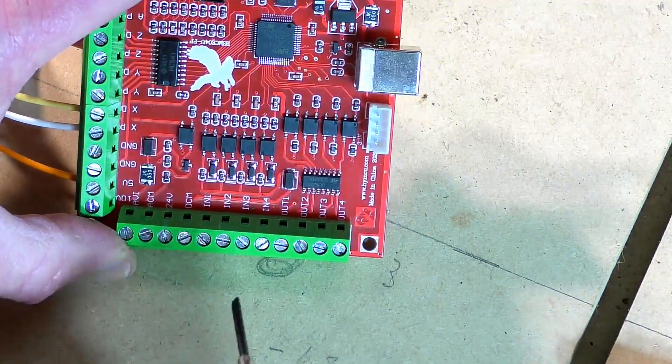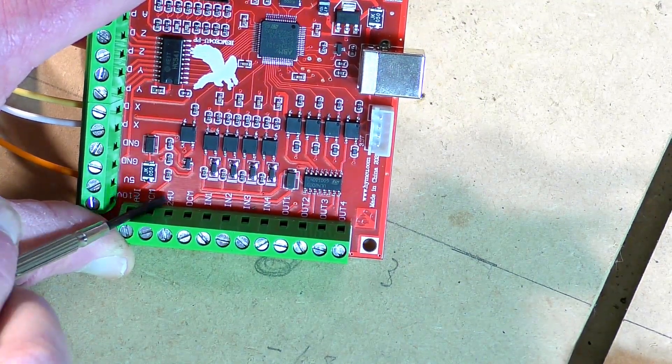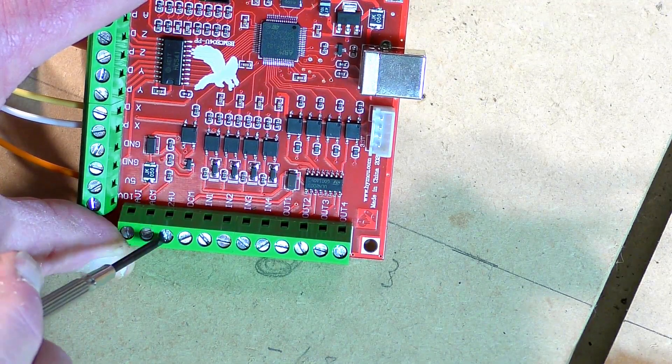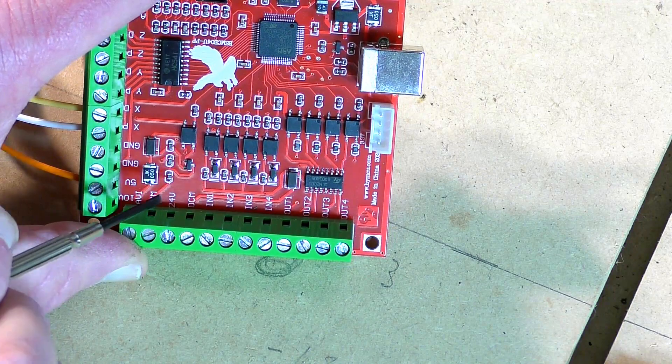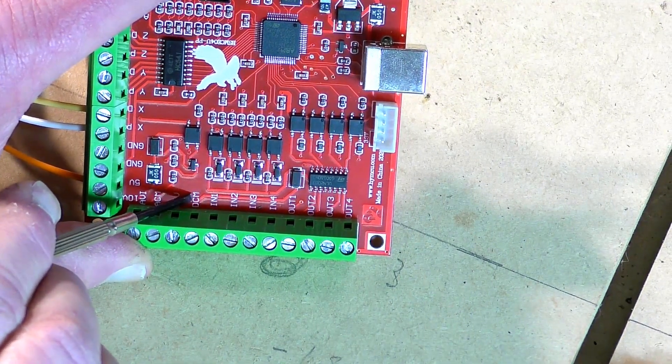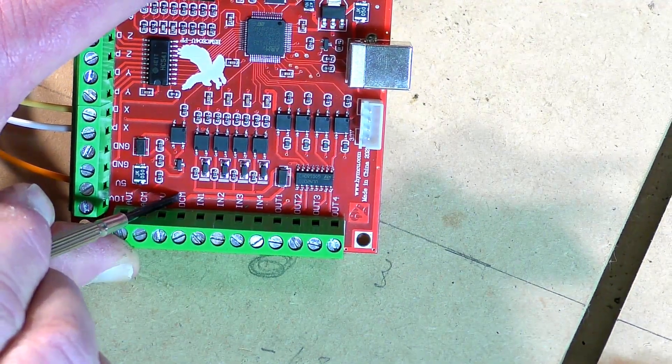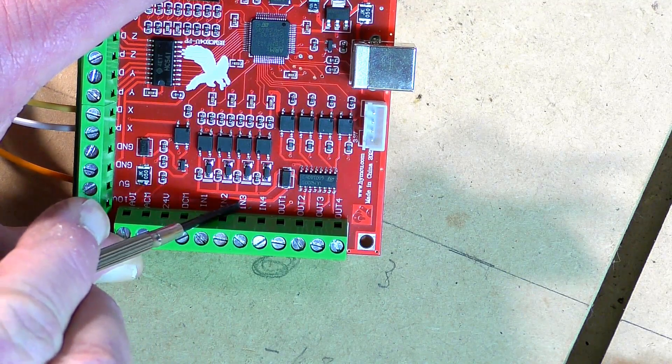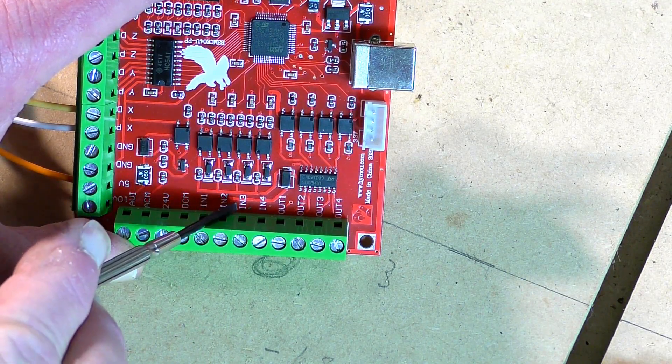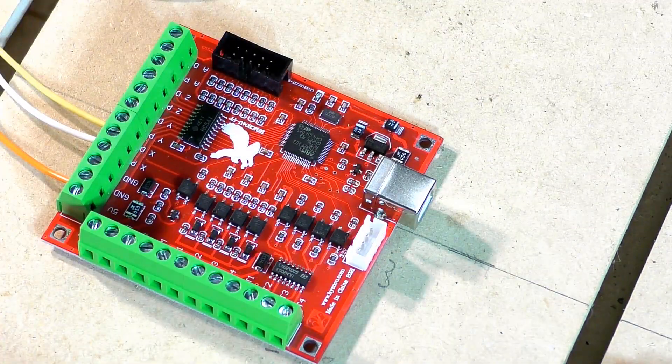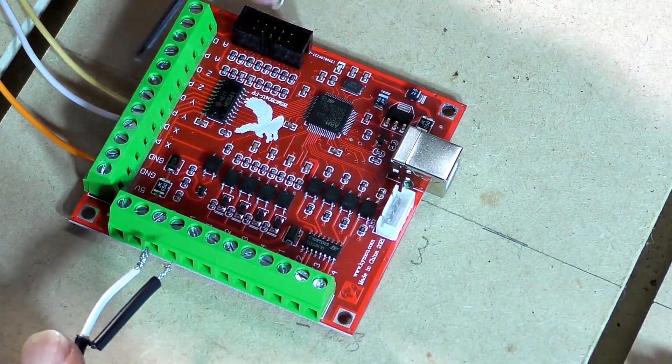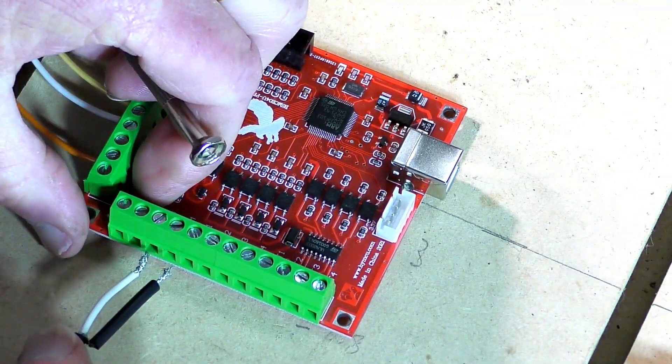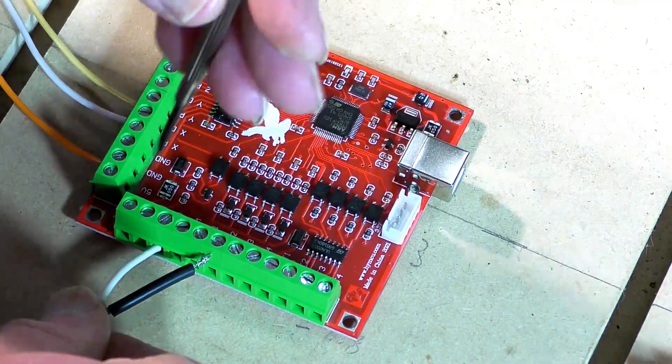This is the 24 volt side. If you notice here, this is 24 volt, this is the positive input. The negative input to this board is DCM which is DC common, and the other side of the switch is pin three. So we're going to connect in on pin three. And this is what it looks like in the wiring. This is the positive going in here on the 24 volt into there.